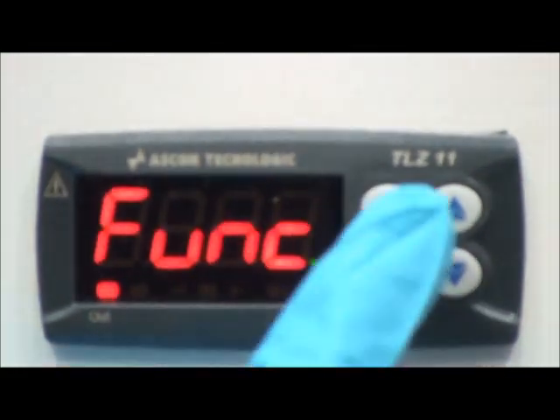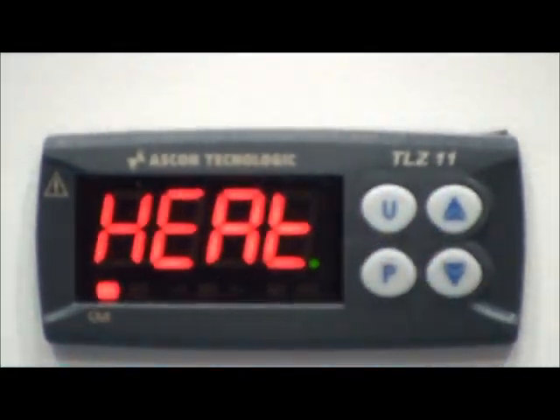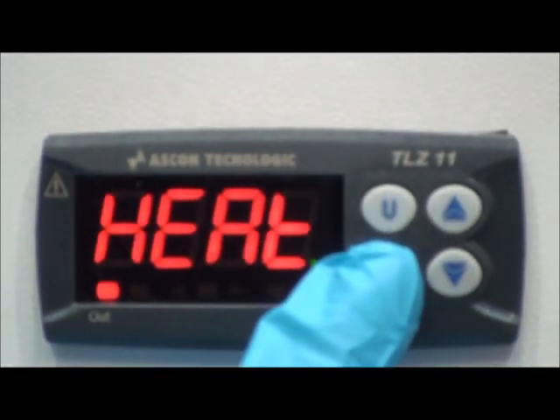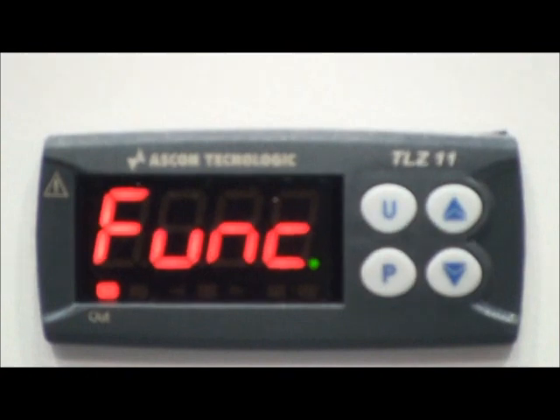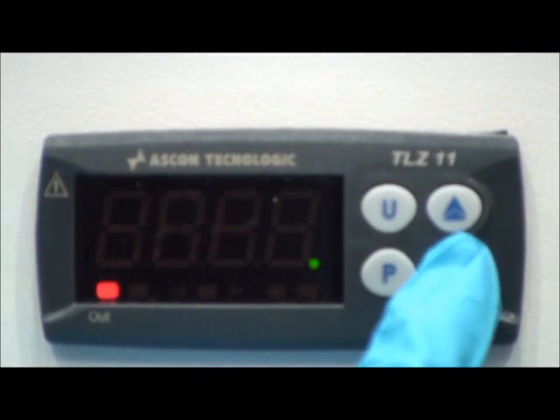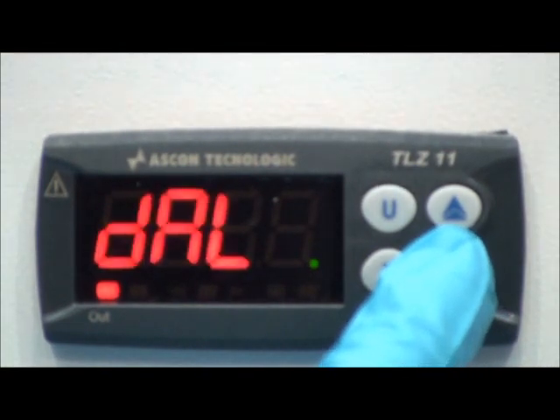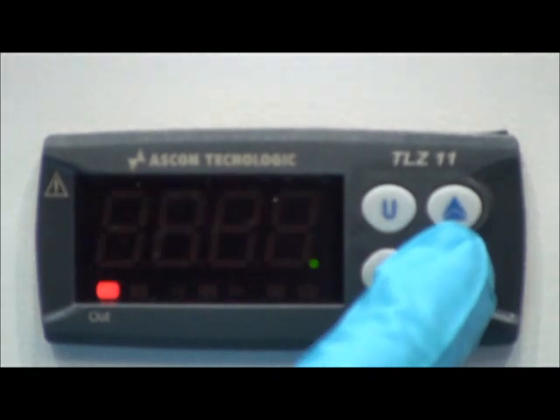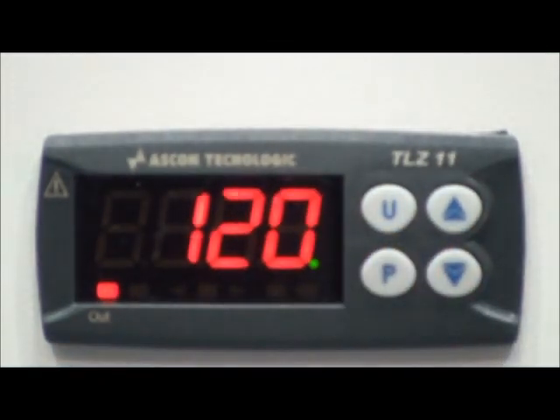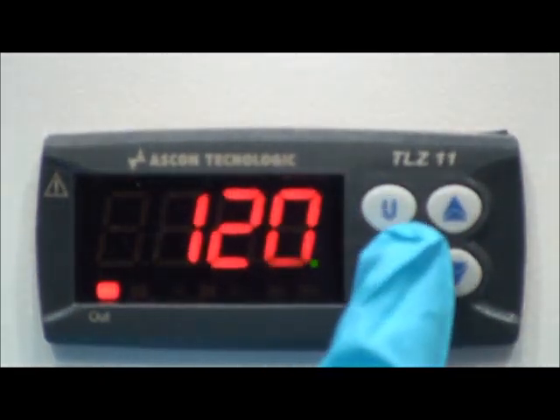Function is to heat. So you have an option with the timer, it's heat or cool. In this instance, we're obviously using it to heat. And then finally, you will go down to the set point, which is SP. There it is, and it's set at 120, so P accepts that. If you leave it now for 5 or 10 seconds, it comes back into normal operation.